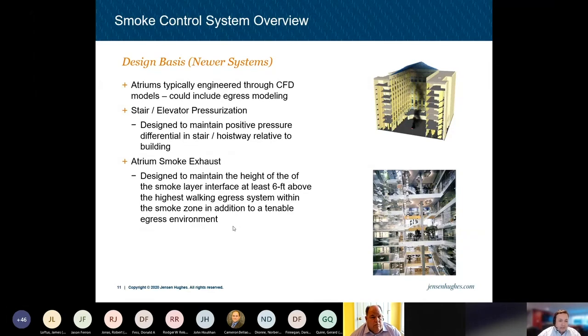An atrium smoke exhaust is designed to, under current code, maintain the height of the smoke layer interface at least 6 feet above the highest walking egress surface within the smoke zone, in addition to a tenable egress environment. And a tenable environment would be temperature, visibility, and carbon monoxide. Older atrium systems, you'll see that they were designed for an air change per hour based upon the atrium size or height.